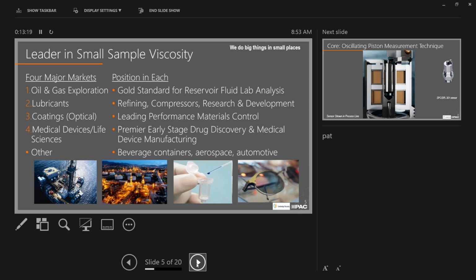So that's another benefit. But also, for maintaining or testing the performance of these devices to test their accuracy, you just remove them from the line and put in a milliliter of fluid, and you can test their operation. With other types of technology, where you have a probe that is 30 centimeters long, the amount of expensive viscosity calibration testing oil required is going to be significantly more, possibly a liter or more. So being small is a very, very good thing in this industry. And we believe that we're doing big things in small places.